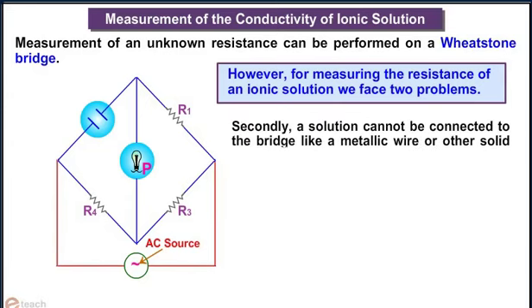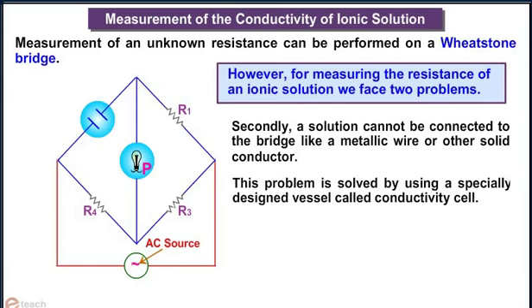Secondly, a solution cannot be connected to the bridge like a metallic wire or other solid conductor. This problem is solved by using a specially designed vessel called conductivity cell.